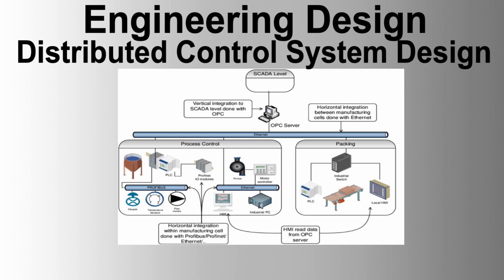The execution rate for fast loops should be a minimum of 0.25 seconds, and for slow loops not exceeding 1 second. 9. DCS I/O processor modules will match the input and output counts listed with an additional 20% margin for fully wired installed spares. 10. The system mass memory will hold all system and application software and database, capable of holding configuration information for future application programming and configuration.